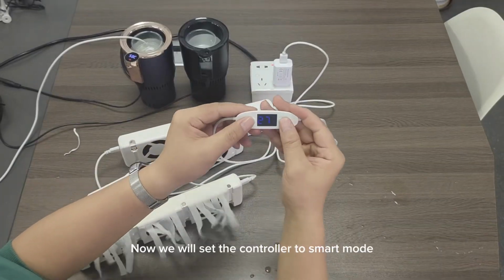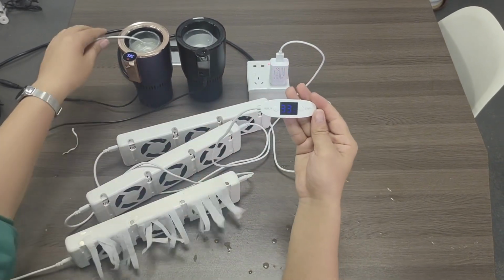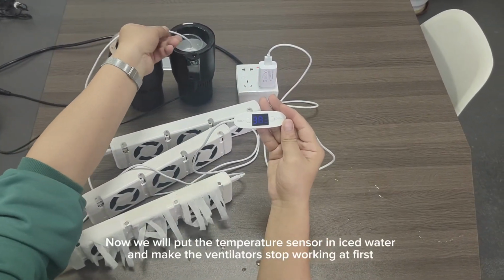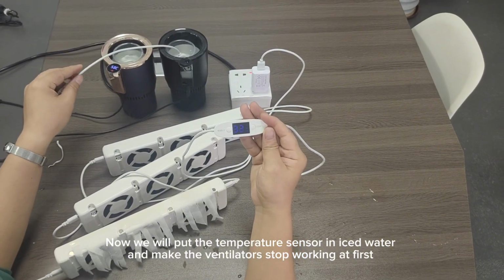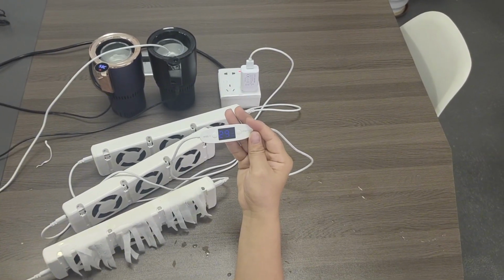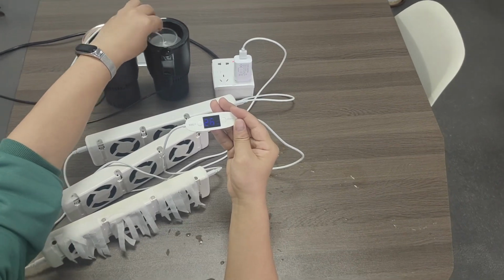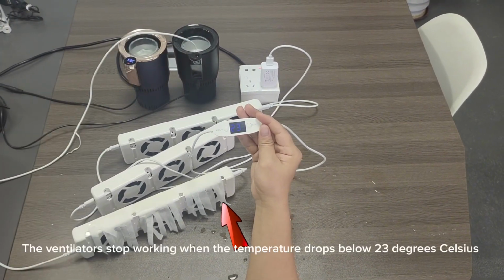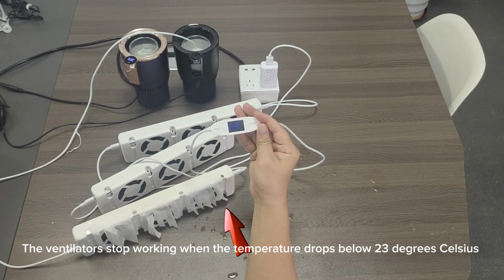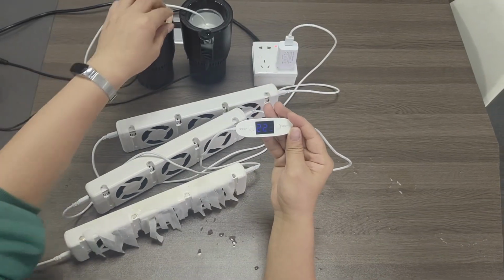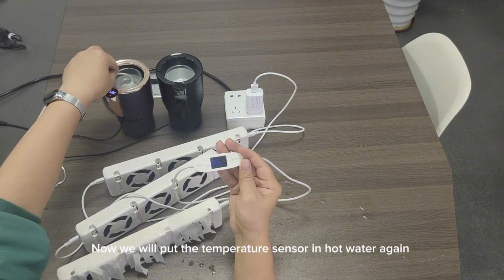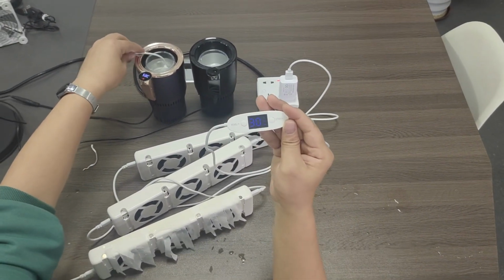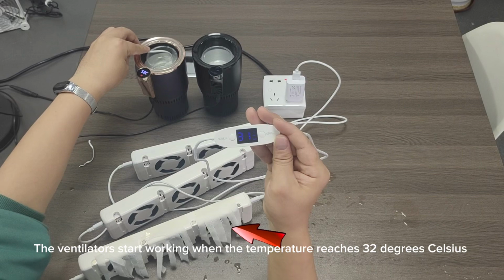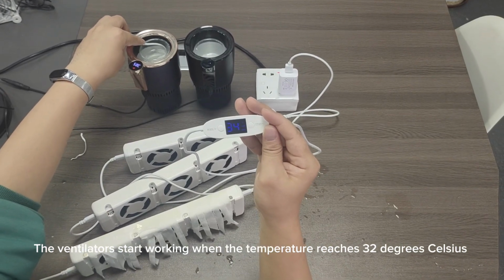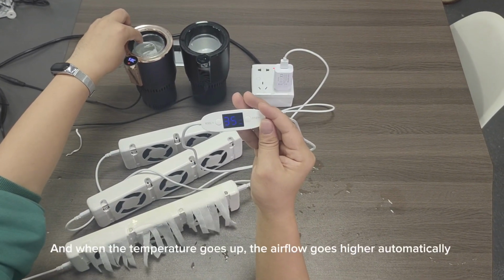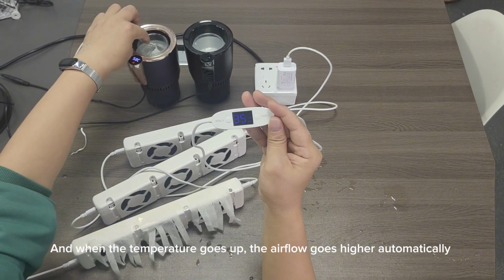Now we will set the controller to smart mode. Now we will put the temperature sensor in iced water and make the ventilator stop working at first. The temperature goes lower and lower. The ventilators stop working when the temperature drops below 23 degrees Celsius. Now we will put the temperature sensor in hot water again. The ventilators start working when the temperature reaches 32 degrees Celsius. And when the temperature goes up, the airflow goes higher automatically.